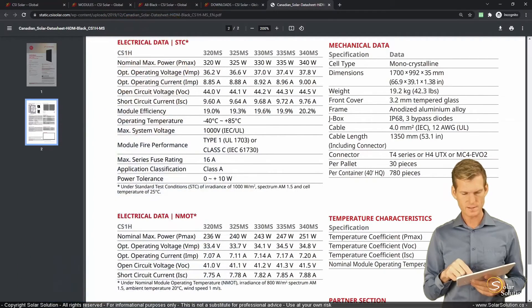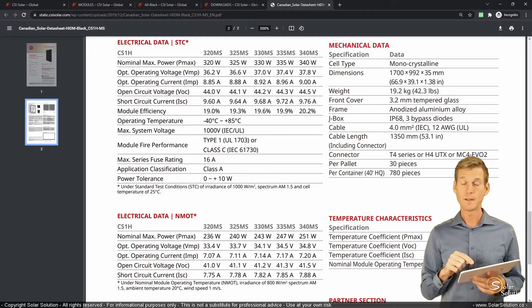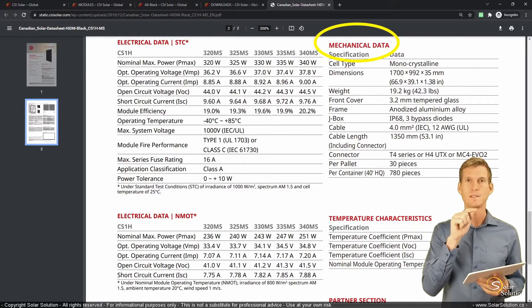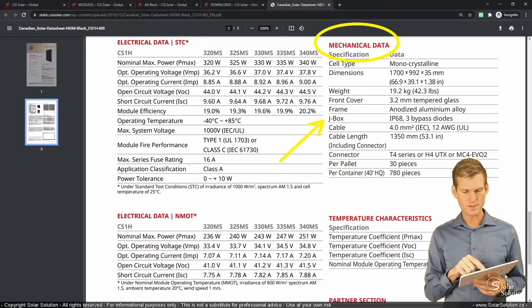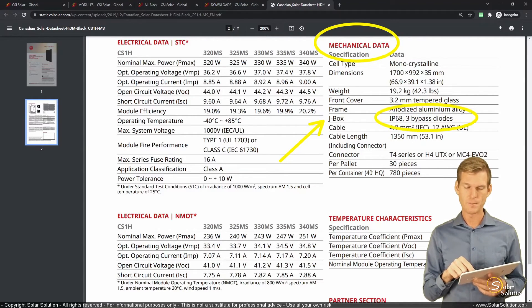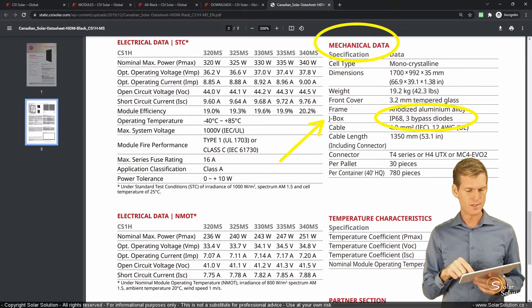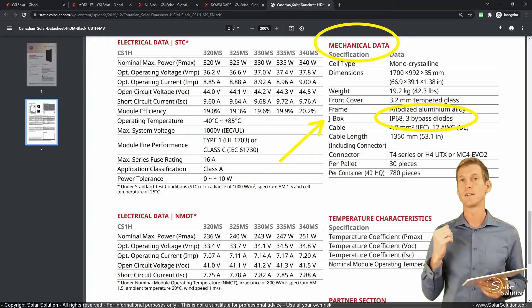But for this manufacturer, it says it on the second page of the specification sheet, in the section of mechanical data, and you're looking for, it's normally expressed in the section on the junction box. So here on the junction box, or J box, it says that it has three bypass diodes. So it doesn't tell us exactly what the internal wiring looks like, but it's safe to assume that if it's a 60-cell module and it has three bypass diodes, that is configured in the way as we just looked at before.